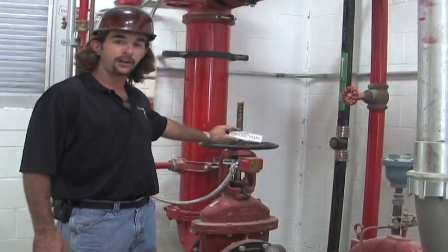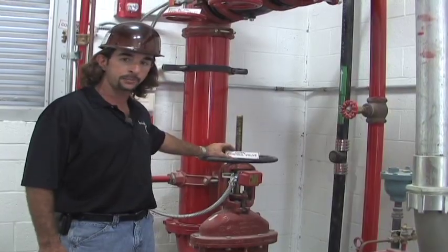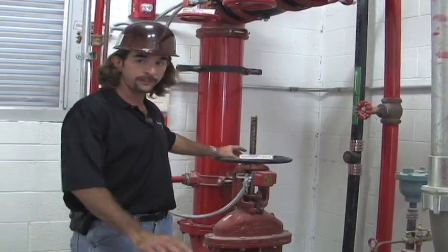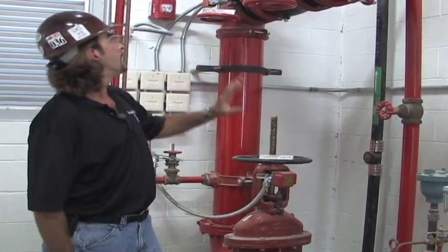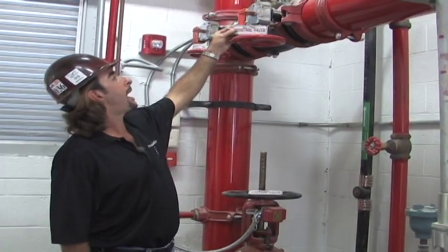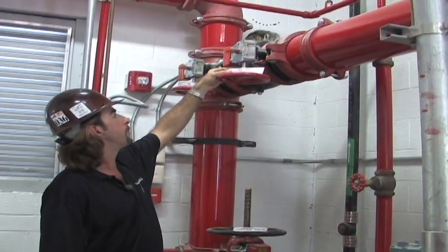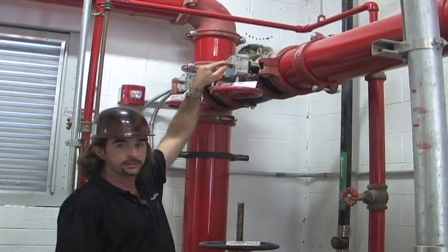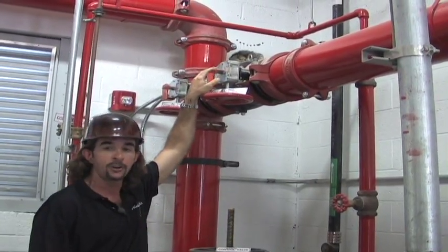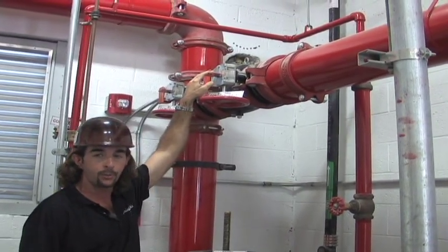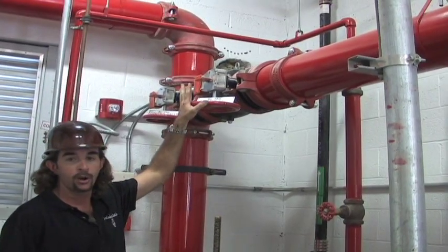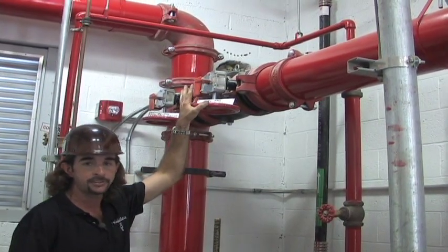This is going to be our valve, our main valve coming in from the underground supply, feeding our electric fire pump. We have two bypass valves, control valves. Both of them are going to stay in the open position. In case for some reason our fire pump didn't come on or was not working, city water would still come through this, bypassing the electric fire pump.